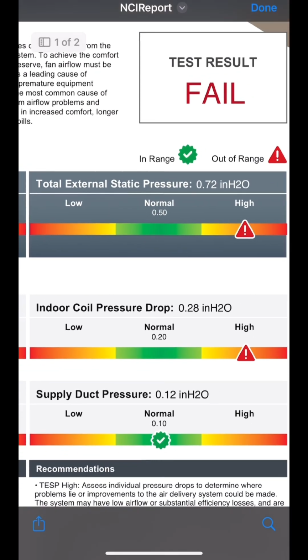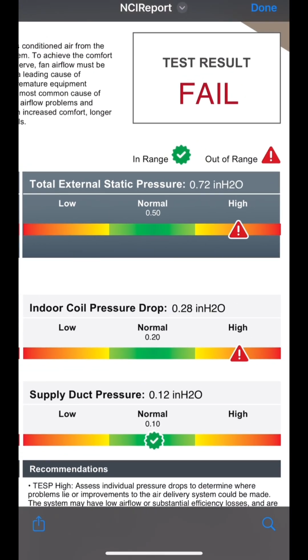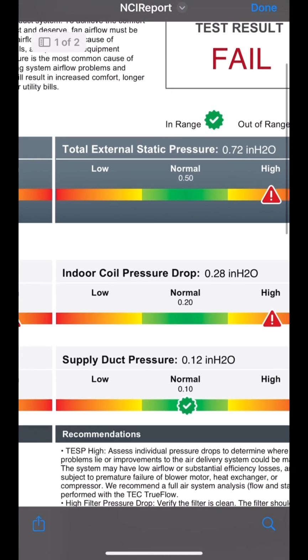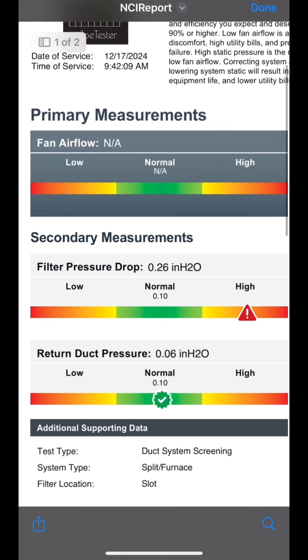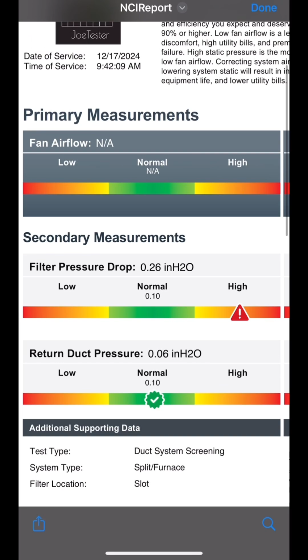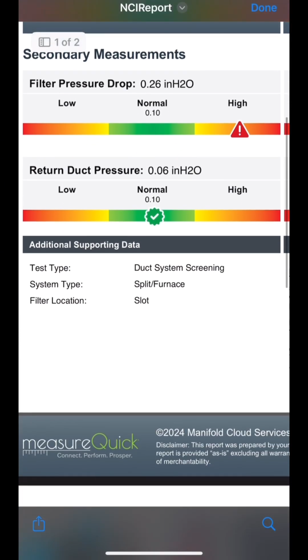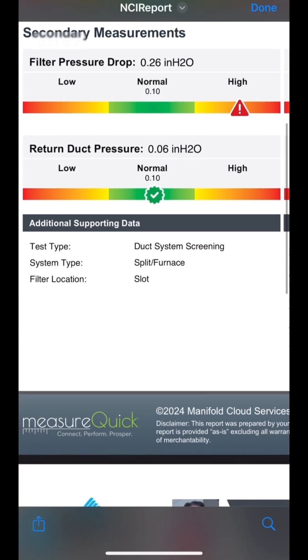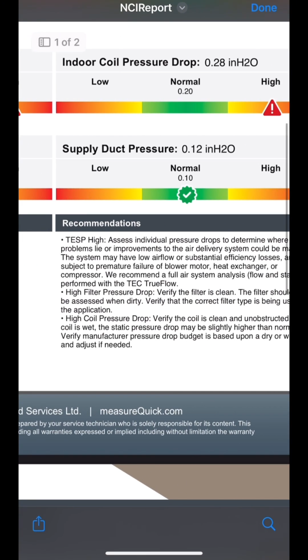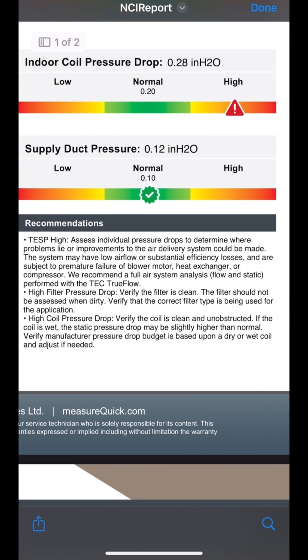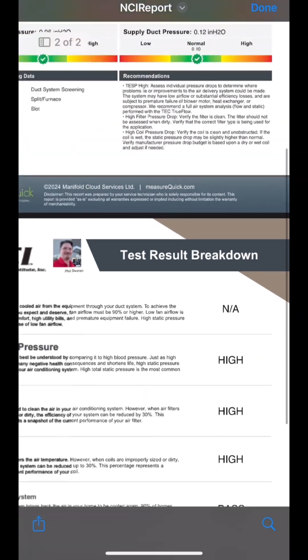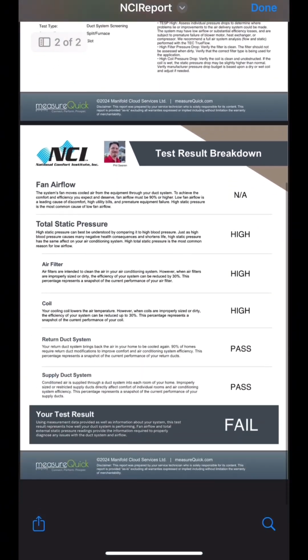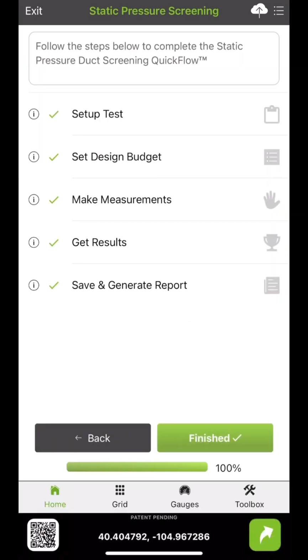It shows that my external static is out of range. Nice, easy to see. Red triangle. My coil pressure drop is out of range. Over here, we see my filter pressure drop is out of range. We know that I'm looking at the right kind of system. My return duct is okay. My supply duct is okay. And then when we look over here, I have recommendations. Like, this is not me telling you you need to fix and clean the coil. This is a third party, and this is why.